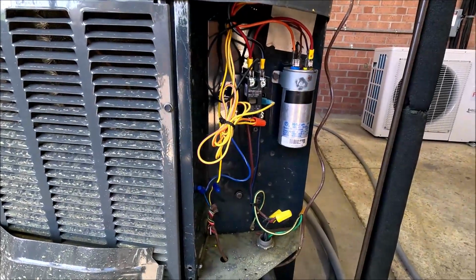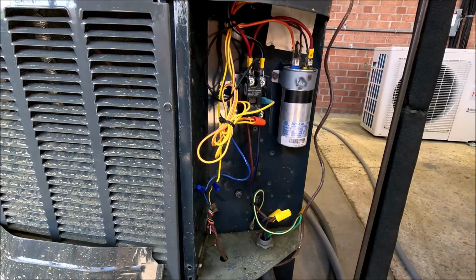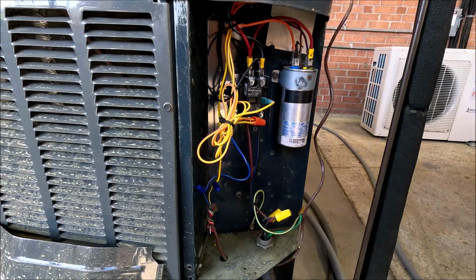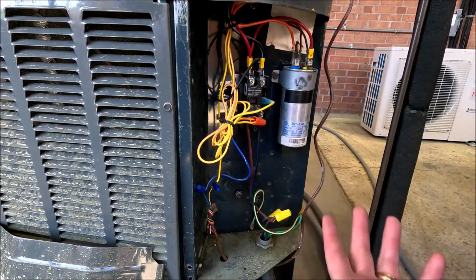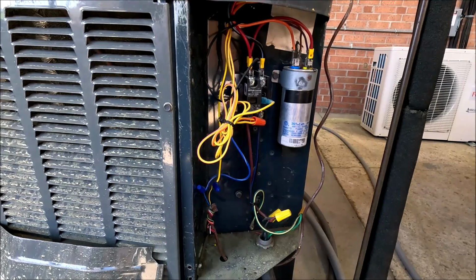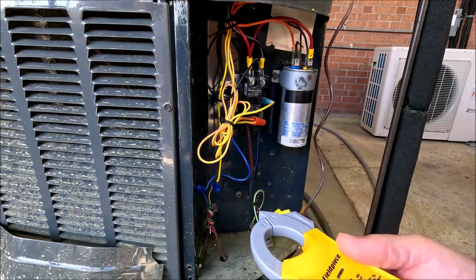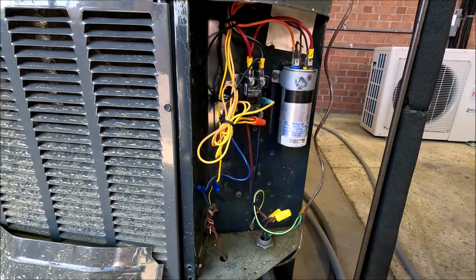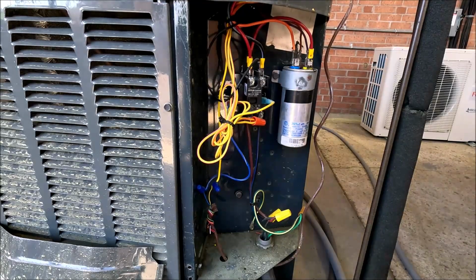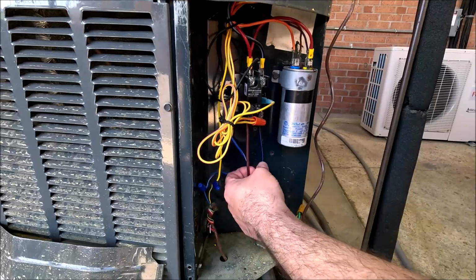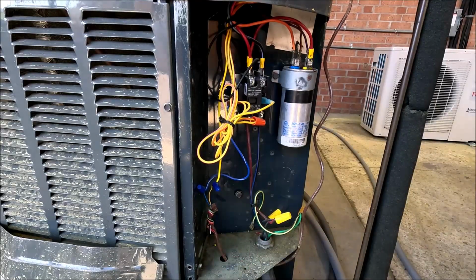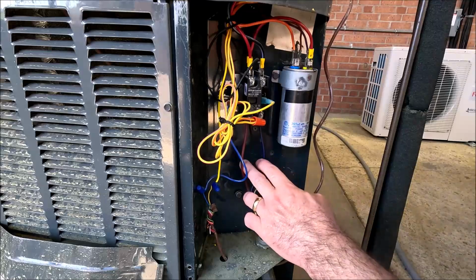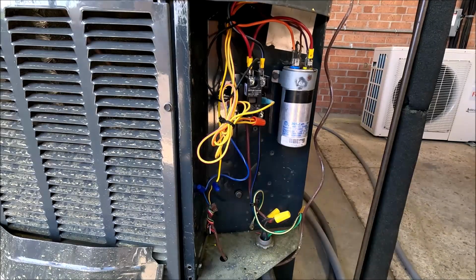So for what I got here, this is the Trane unit that went with the furnace that I was just looking at with the 2-stage or 2-speed inducer motor. And once we get into air conditioners with a lot more wiring, then we have to be careful. You have to watch. So of course I've got my L1, L2 coming in, and there's a red and a black wire. Typically, if you're on a Goodman, it might be yellow and black, or a Ruud, it might be orange and black, or something like that. But whatever it is, you're going to have L1, L2, and this is a 208 system that we're on.